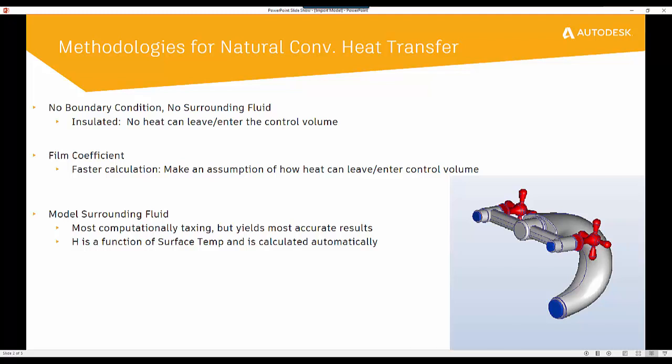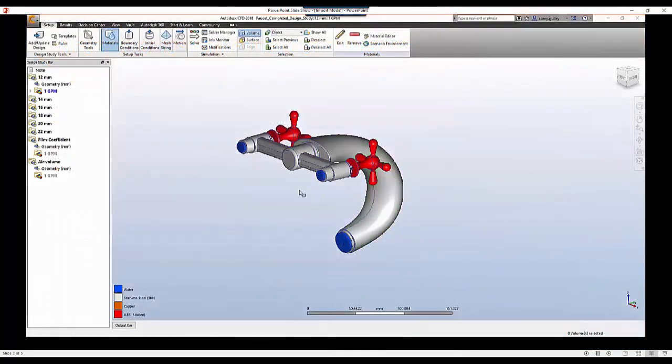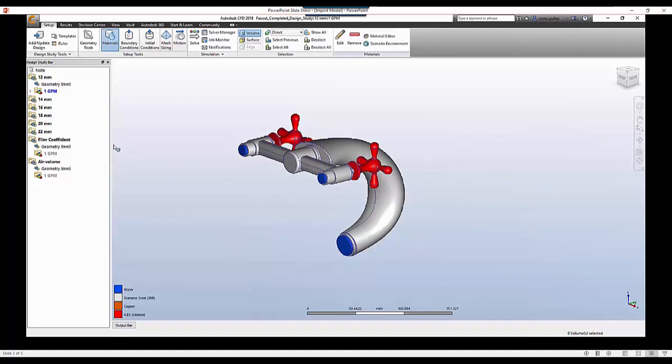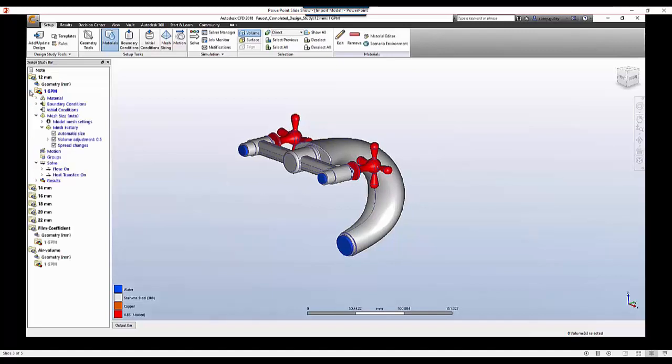But the beauty of this is that it automatically will calculate those film coefficients at the node for us automatically. It does this because it understands what that temperature surface value is on the outside surrounding of the model, and then by effect it will provide a film coefficient. So we're obviously going to have the most accurate values that way.